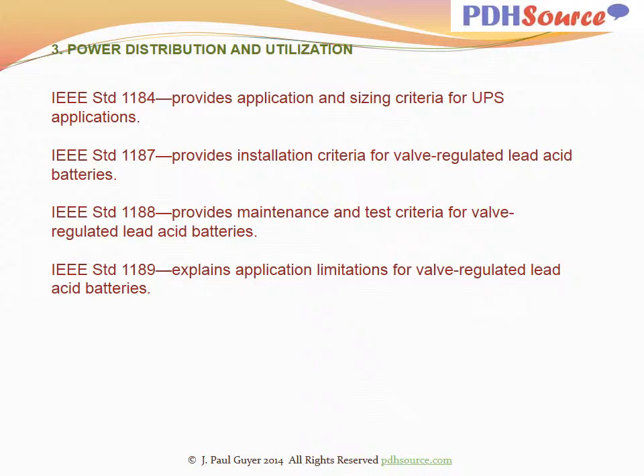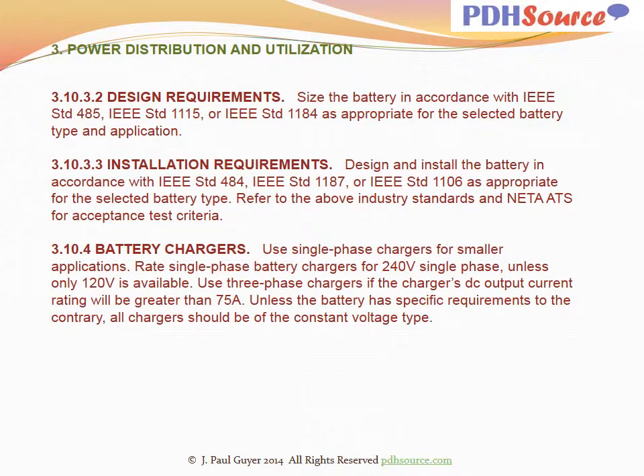IEEE standard 1188 provides maintenance and test criteria for valve-regulated lead-acid batteries, and IEEE standard 1189 explains application limitations for valve-regulated lead-acid batteries. Size the battery in accordance with IEEE standard 485, 1115, or 1184 as appropriate for the selected battery type and application. Design and install the battery in accordance with IEEE standard 484, 1187, or 1106 as appropriate for the selected battery type. Refer to the above industry standards and NETA ATS for acceptance test criteria.